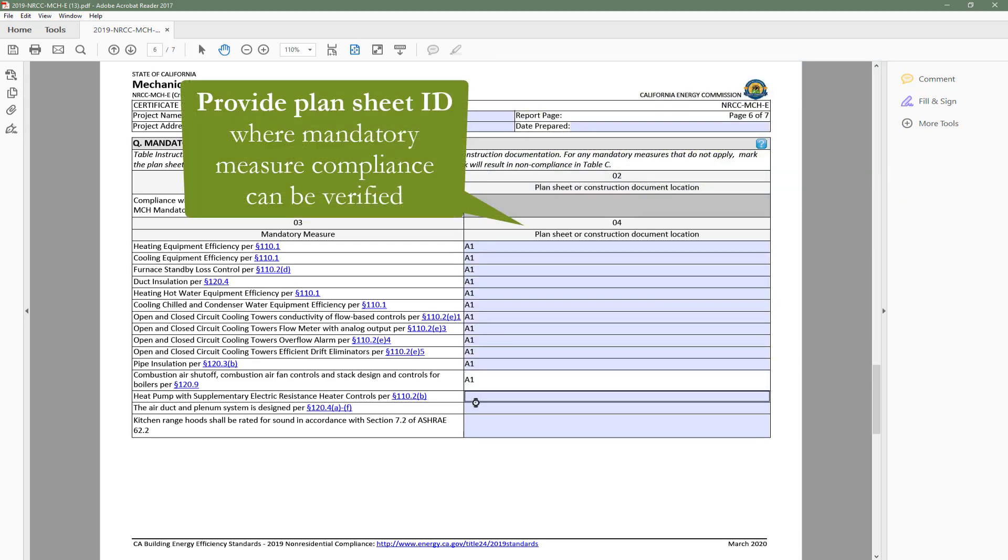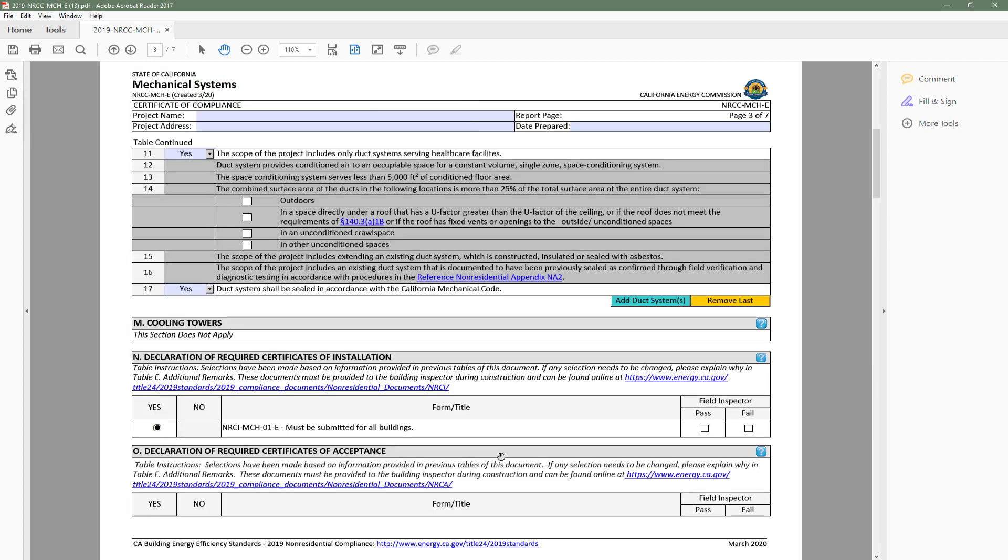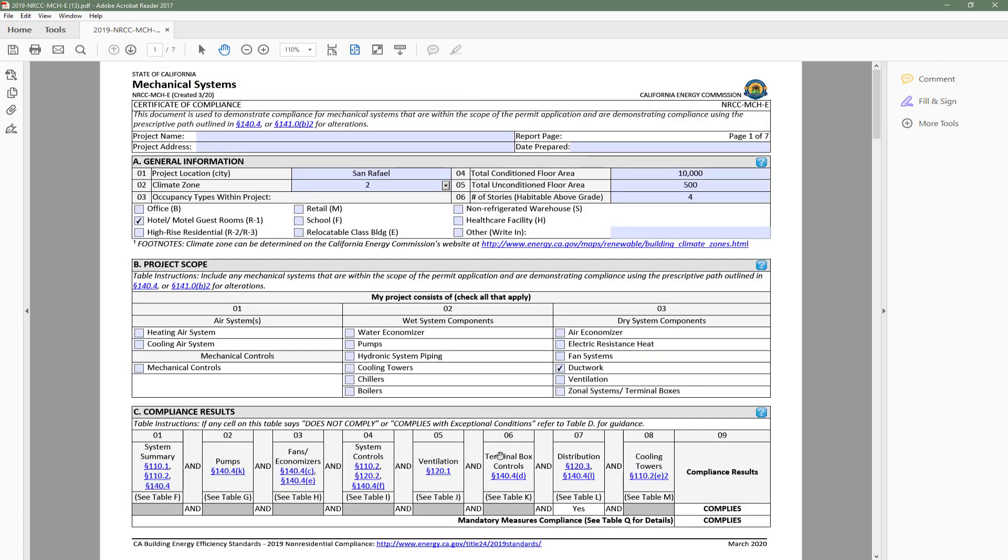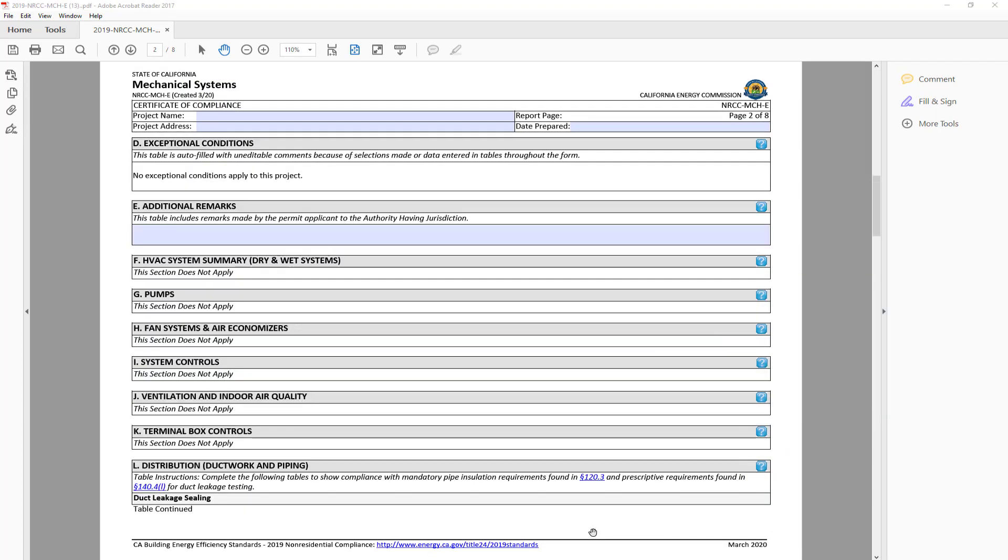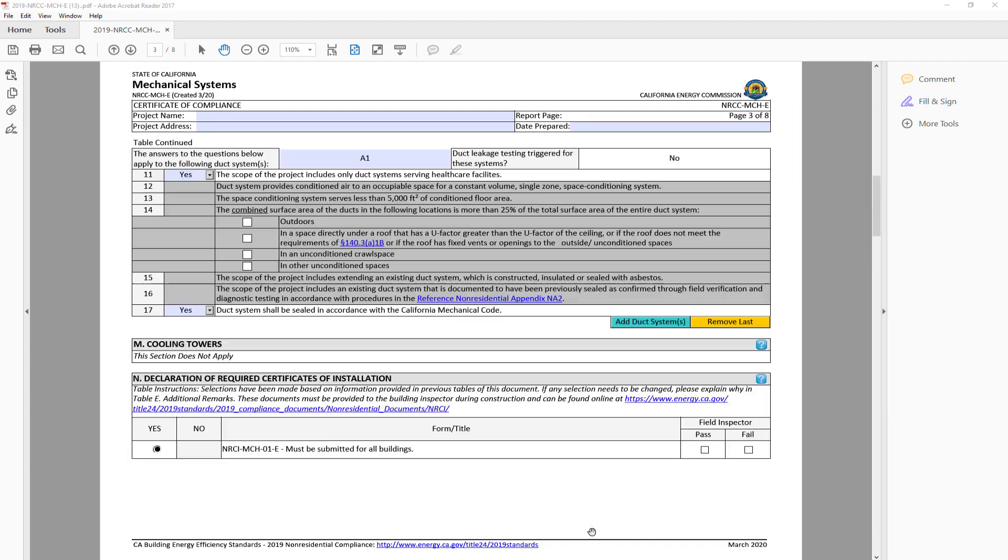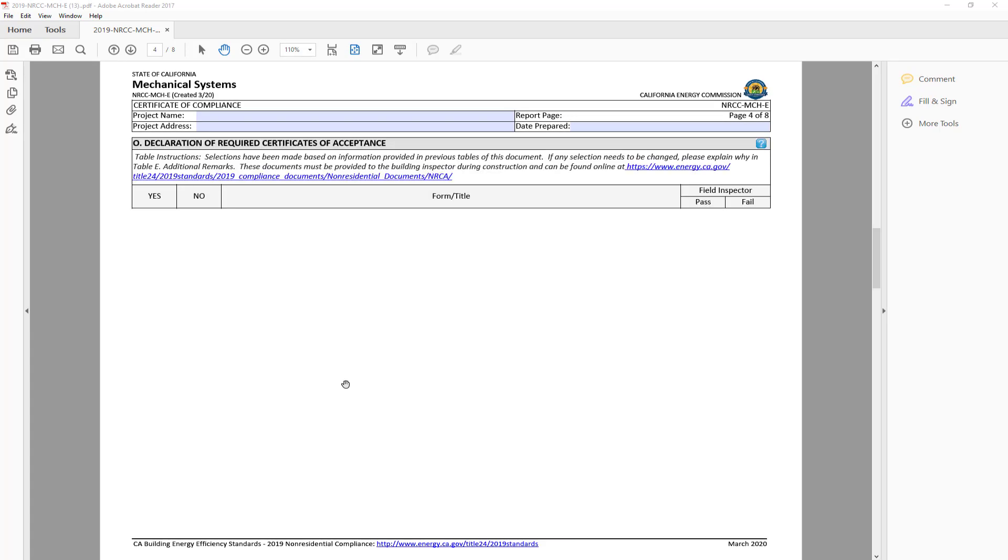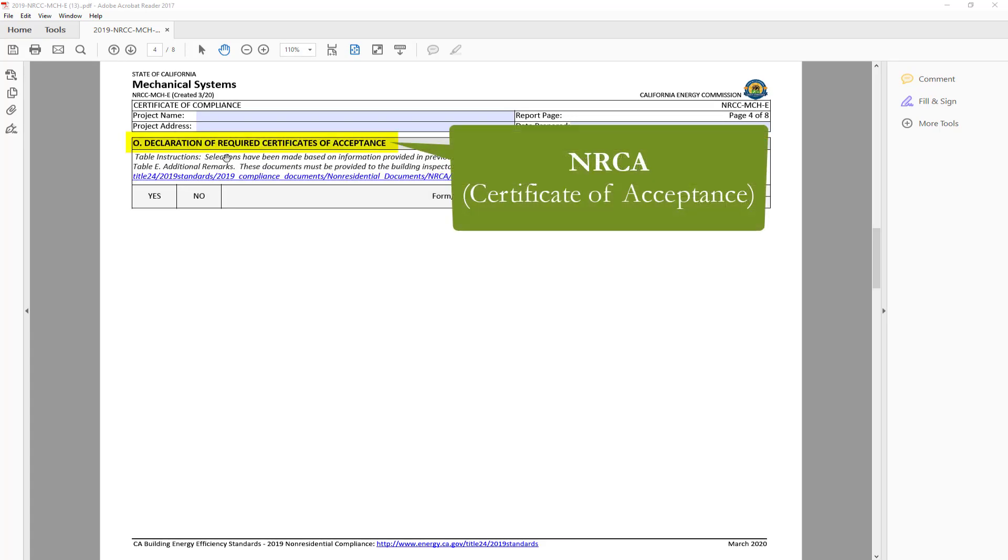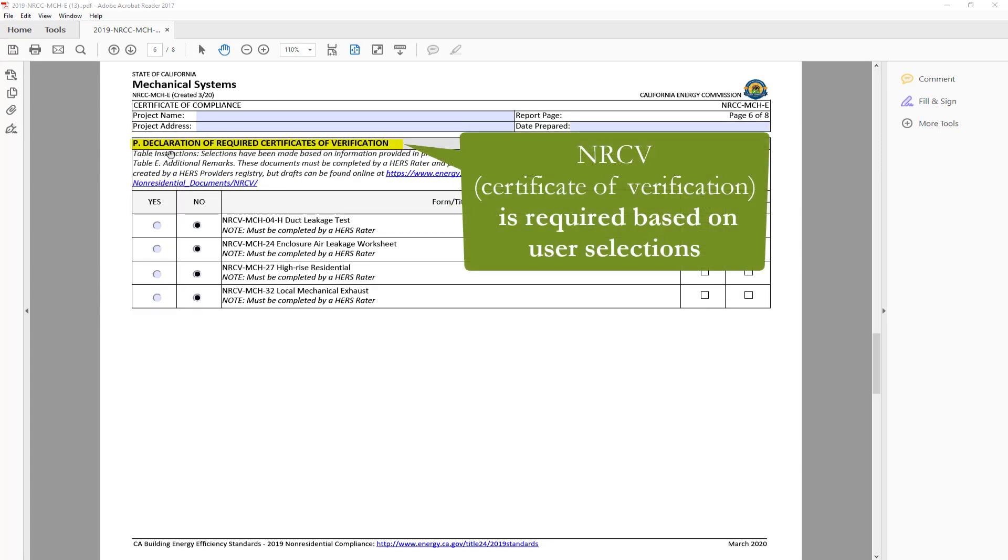Once Table Q is complete, we will head back to Table C and find that the Mandatory Measure row indicates complies. Another great feature of the dynamic forms is the ability to indicate which NRCI or Certificate of Installation, NRCA or Certificate of Acceptance, as well as NRCV or Certificate of Verification is required based on building type and scope of work.